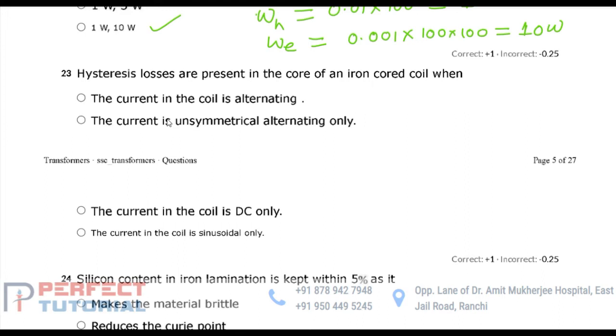Say whenever alternating nature of flux is impressed to core, yes, there would be the magnetization and demagnetization process associated to the core, and that causes the hysteresis loss in core. So the fundamental reason or the fundamental cause of the occurrence of the hysteresis loss here is the presence of the alternating nature of exciting current to the core. So the correct answer would be the current in the coil is alternating.